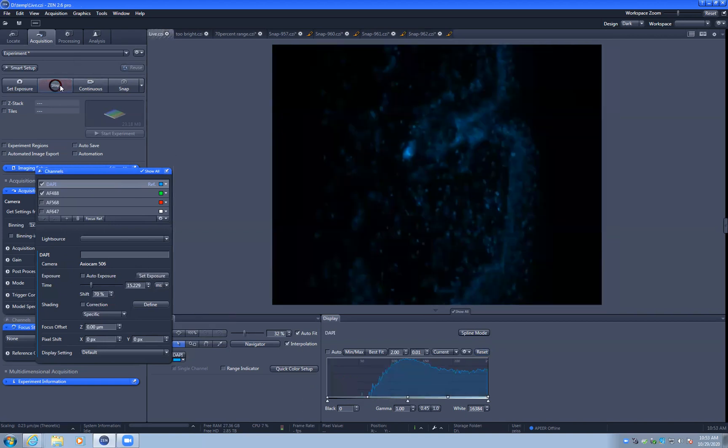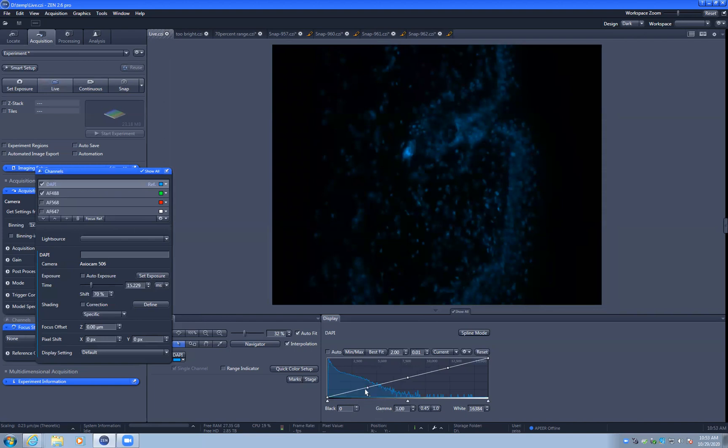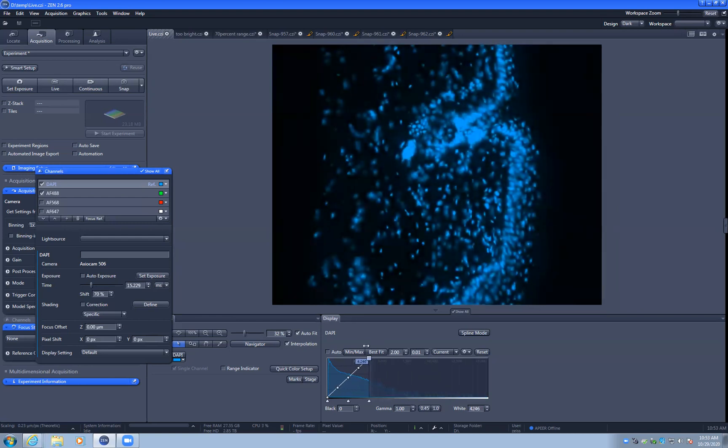So we would want to go through and do this for every color. Let's go to DAPI. And you don't even have to hit live to do this. We can just say that we're going to go for 70%, auto exposure, and set exposure. And you can see it did a great job. And again, you may have some nuclei that are dimmer later on. You can say for display, you want to crank it brighter, because that's the way you like the aesthetics of the image. I don't like it that way, but a lot of people love this high contrast.